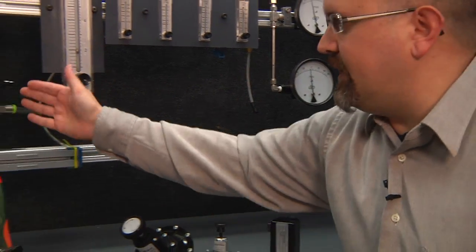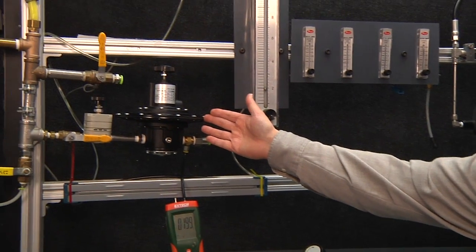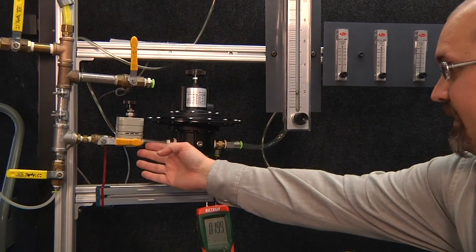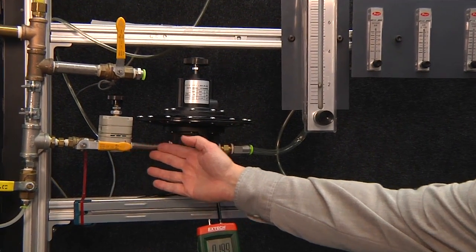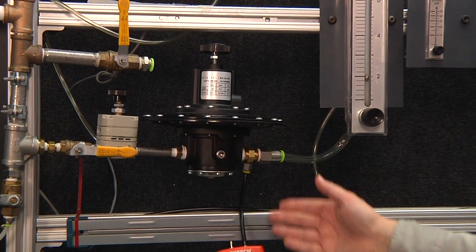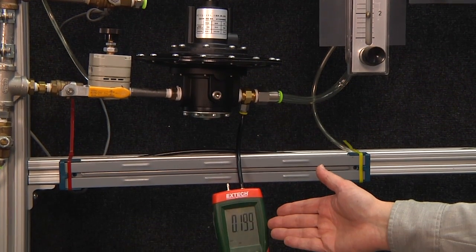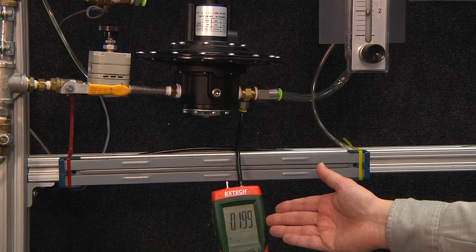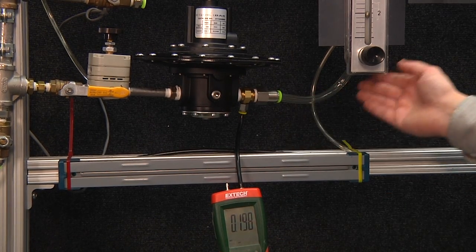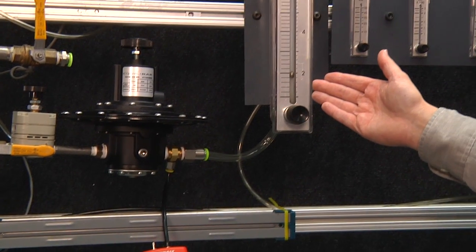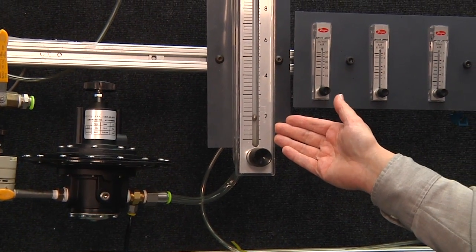I've actually got one in operation right here. This Equilibar regulator has standard industrial shop air being supplied to it. It's got a 0.2 psi setpoint, that's about six inches of water column, and it's controlling at a flow rate of about two SCFM at a fairly high flow.